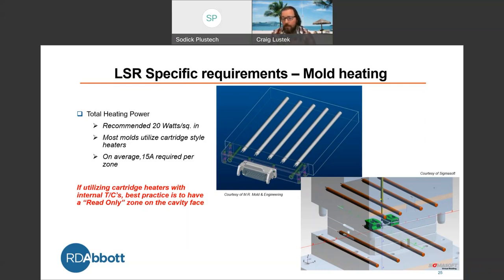A lot of the newer heaters out there, something to watch for, they have internal thermocouples, which are nice, but as soon as you turn the mold heats on, within anywhere from 5 to 15 minutes, it'll tell you your mold's up to temp. I always like to have a read-only zone added in the face. Sometimes it can't be done, but if you're able to, I recommend asking for that. That way you can actually see what your cavity face is. We want to make sure that your cavity face is as close to your set point as possible. So if you're asking for 300 degrees Fahrenheit, we're within that 5 to 7 degree range on that cavity set.